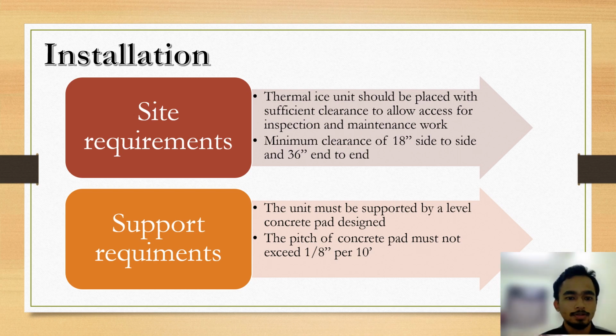So these are the other two requirements for installation. For site requirements, the thermal ice unit should be placed with sufficient clearance to allow access for inspection and maintenance work, and the minimum clearance of 18 inches side to side and 36 inches end to end is required. As for the support requirement, the unit must be supported by a level concrete pad, and the pitch of the concrete pad must not exceed 1/8 inch per 10 feet.